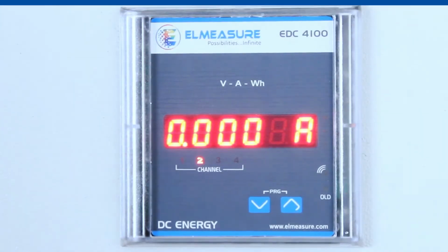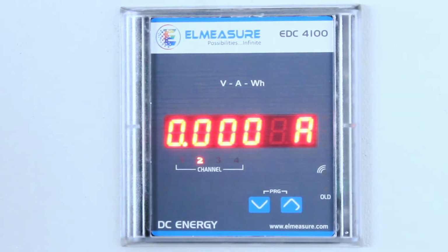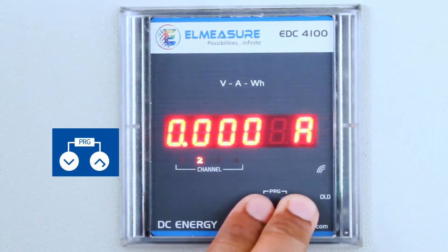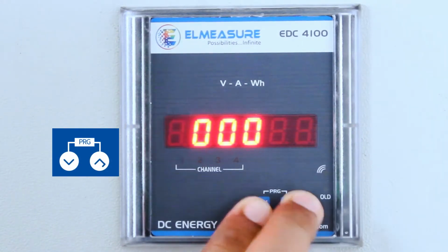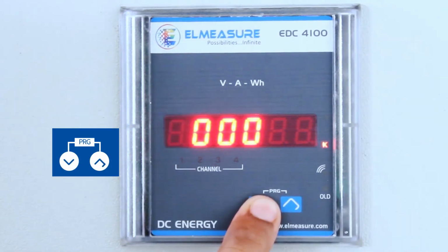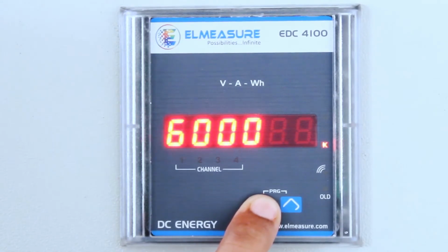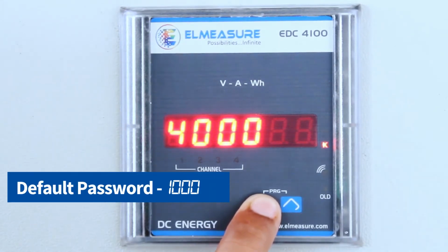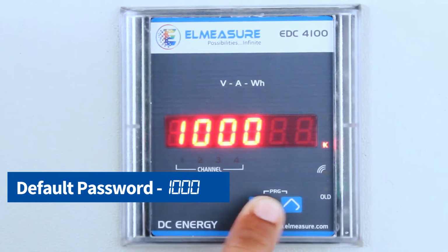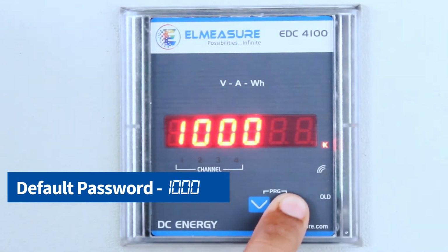Let's configure EDC 4100. Once you power on the meter, press both these buttons at the same time. This initiates the meter's configuration mode, and asks you to enter the device's passcode. The default factory set passcode is 1000. Set this code using the scroll down key and press the right enter key.